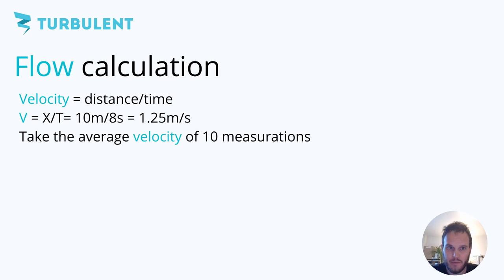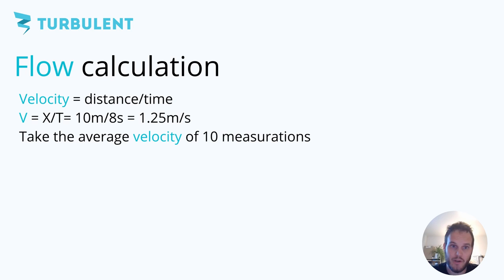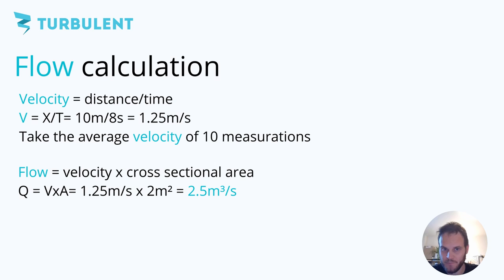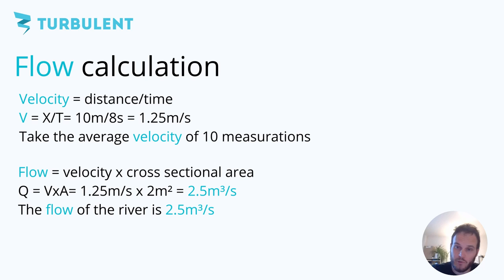But then when you have done this you can use that average velocity together with the cross-sectional area that you have measured before to calculate your river flow because the river flow is equal to the velocity of the stream times the cross-sectional area. In the case of our example that was 1.25 meters per second times 2 square meters which is equal to 2.5 cubic meters per second. This is a very respectable flow and you can probably get something like 30 kilowatts out of this if you have 1 or 1.5 meters of head difference.